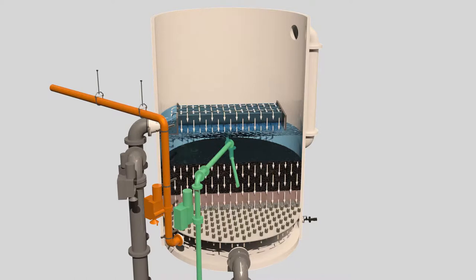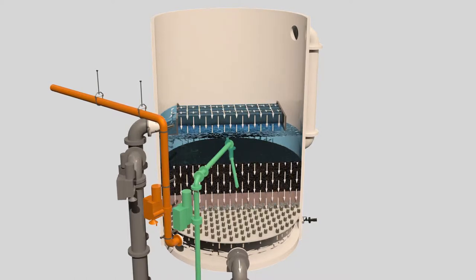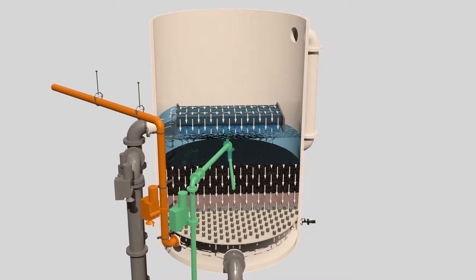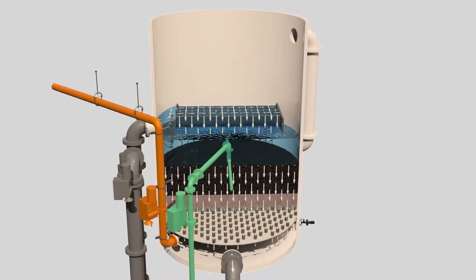Therefore, the media filters are used to remove fine particles that still remain in the solids contact clarifier effluent. This effluent has a pH of around 10.5 to 11.5.